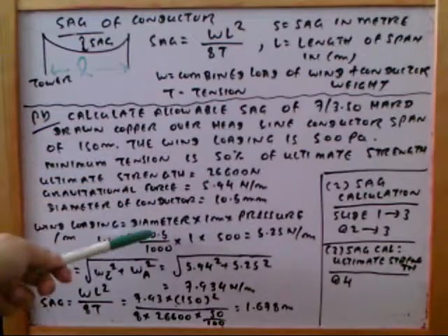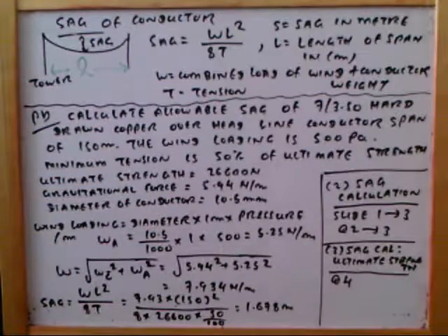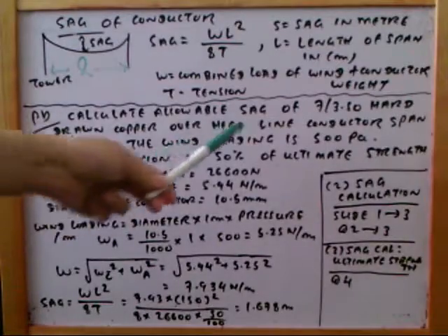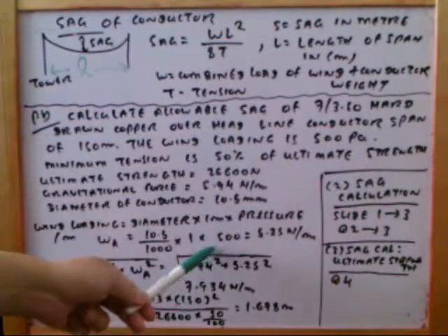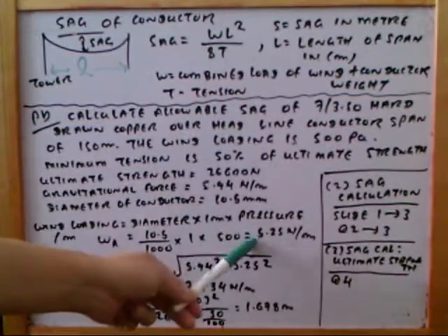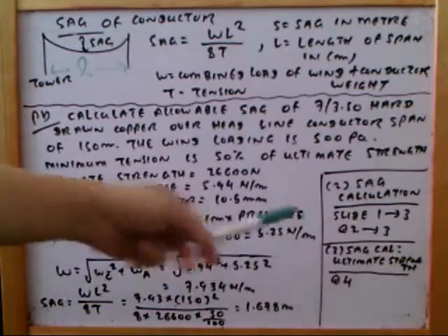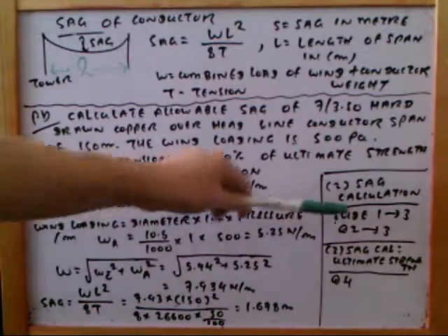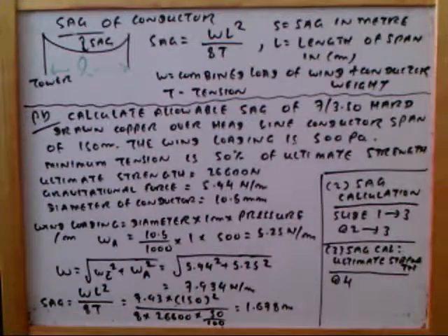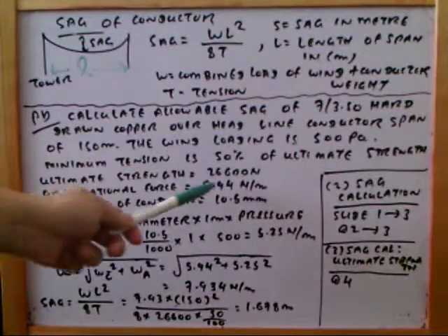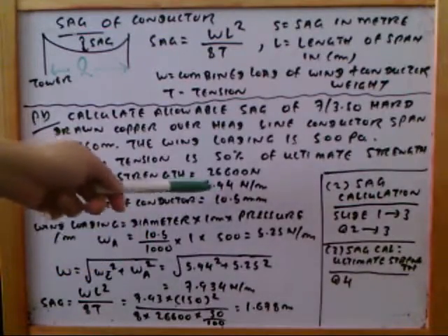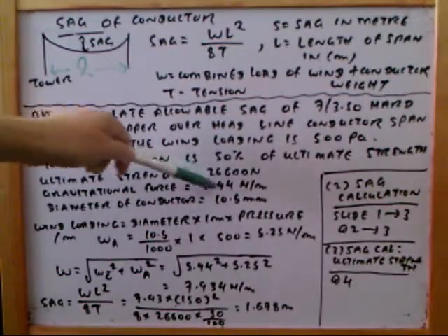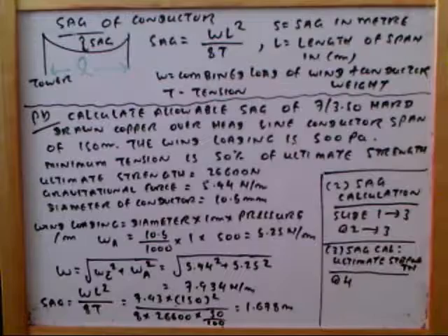The diameter is 10.5 millimeters, which is 10.5/1000 meters, multiplied by 1 meter and the wind pressure of 500 Pa. Solving this gives wa = 5.25 newton per meter. The horizontal wind force is 5.25 N/m, and the gravitational force wc is 5.44 newton per meter.